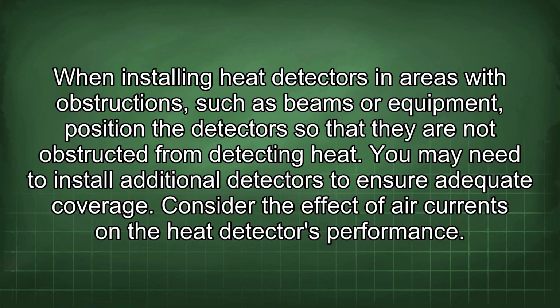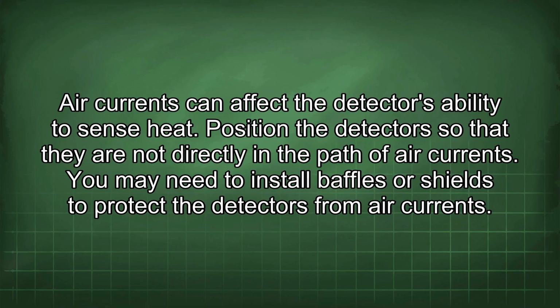Consider the effect of air currents on the heat detector's performance. Air currents can affect the detector's ability to sense heat. Position the detectors so that they are not directly in the path of air currents. You may need to install baffles or shields to protect the detectors from air currents.